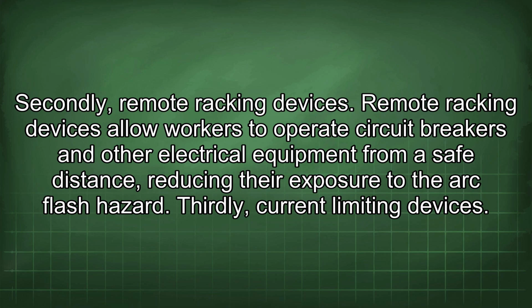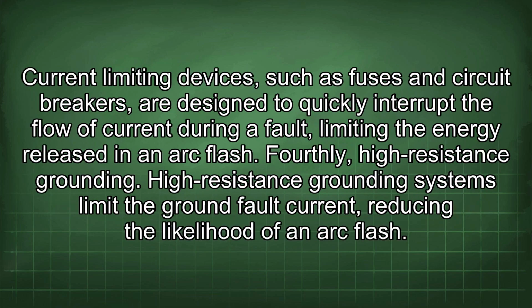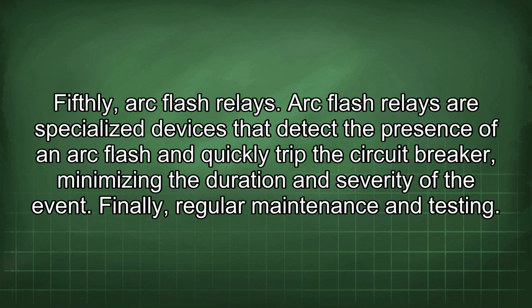Remote racking devices allow workers to operate circuit breakers and other electrical equipment from a safe distance, reducing their exposure to the arc flash hazard. Thirdly, current limiting devices. Current limiting devices, such as fuses and circuit breakers, are designed to quickly interrupt the flow of current during a fault, limiting the energy released in an arc flash. Fourthly, high-resistance grounding. High-resistance grounding systems limit the ground fault current, reducing the likelihood of an arc flash. Fifthly, arc flash relays. Arc flash relays are specialized devices that detect the presence of an arc flash and quickly trip the circuit breaker, minimizing the duration and severity of the event.